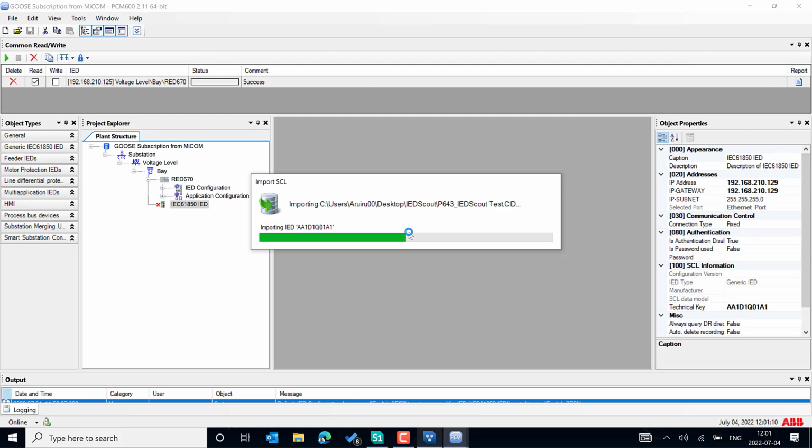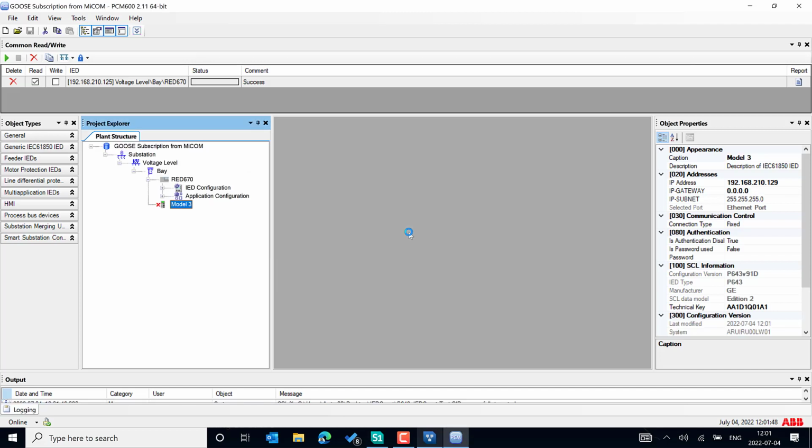That's why in most cases the GOOSE subscription doesn't work when we connect the GOOSE control block from publisher to the subscriber and map to the signal matrix and connect to the function block.